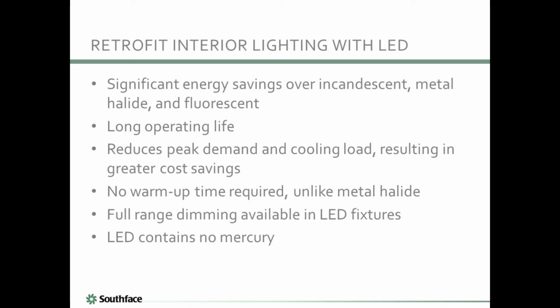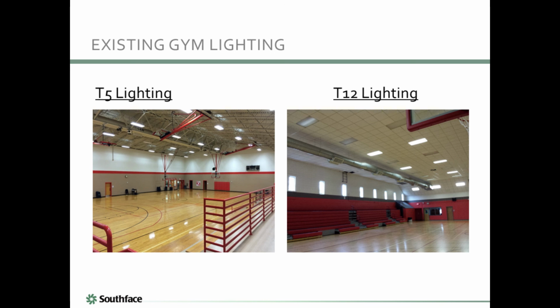The best practices for LED upgrade projects. Purchase LED products that are certified by Energy Star, DesignLights Consortium, or Lighting Design Lab. Always test LED upgrades for a few fixtures at your recreation center before ordering a large quantity of fixtures. Ensure that the upgraded fixtures deliver the appropriate illumination levels, foot-candles. You basically don't want it to be too bright or too dim. One-for-one fixture replacements or lamp-for-lamp replacements may not provide appropriate illumination. Also, combining LED retrofits with occupancy and vacancy controls for rooms with intermittent occupancy can maximize energy savings. Also, be sure to apply for utility rebates to reduce payback.